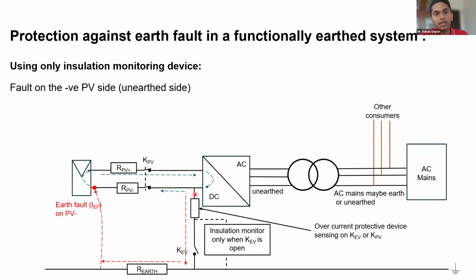If it is low enough, sometimes this overcurrent protective device won't be able to detect it, and if it doesn't detect it, it won't trip. There will be a fault current travelling in the system, but it won't be able to trip. But in these cases, whenever your system is de-energized, like after the day's work and at night time, a maintenance person has to go to the system and check the insulation monitor. If he checks the insulation monitor at that time, he'll be able to know that there is a fault here.